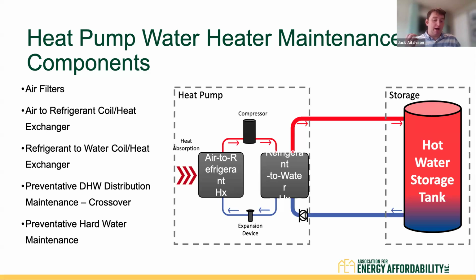I will say heat pump water heaters are more complicated in terms of just the technology, and so typically these are harder to maintain than an HVAC heat pump. Other things to be considered: DHW distribution maintenance. So, crossover is the unintended mixing of hot and cold water in your hot water distribution. This is not specific to heat pump water heaters. This can happen in all buildings, and usually happens at shower cartridges or mixing valves where they have failed and cold water is leaking into the hot water line. However, it disproportionately impacts the efficiency of heat pump water heaters more than gas.